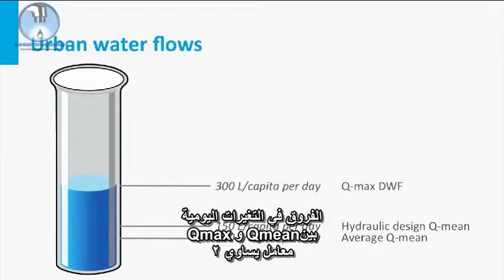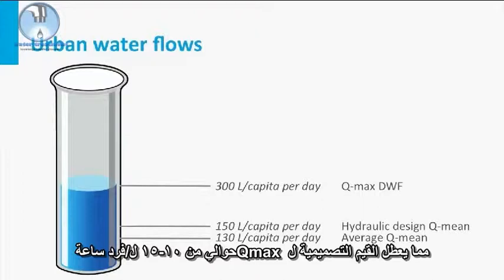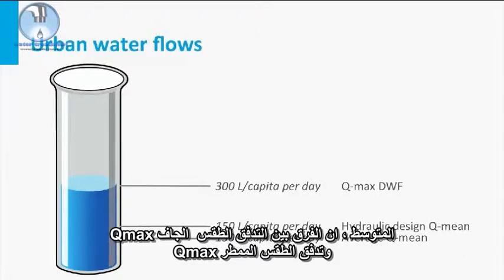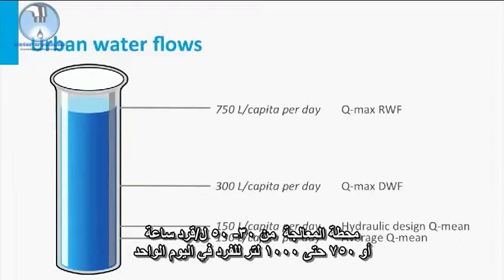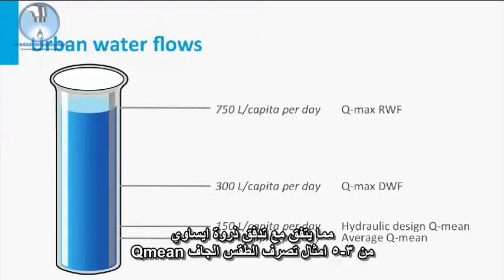The difference between the diurnal fluctuations between Q-mean and Q-max gives design Q-max values between 10 to 15 liter per capita per hour. On average, the difference between the dry weather flow Q-max and the rain weather flow Q-max, or peak flow, is again a factor of 2.5, indicating a maximum hydraulic capacity of the STP of 30 to 50 liter per capita per hour, or 750 up to 1000 liter per capita per day. This agrees with the peak flow being 3 to 5 times the dry weather flow Q-mean.